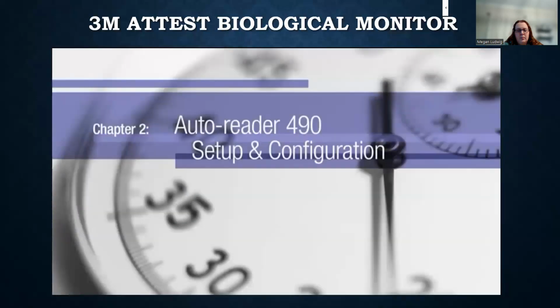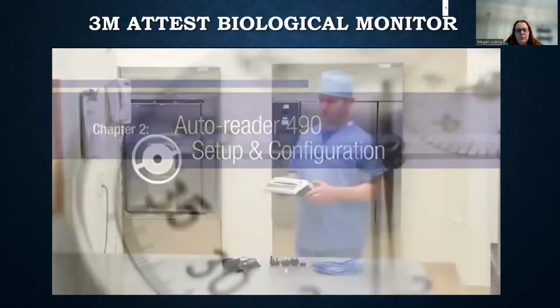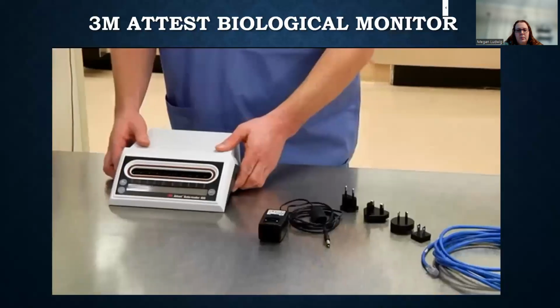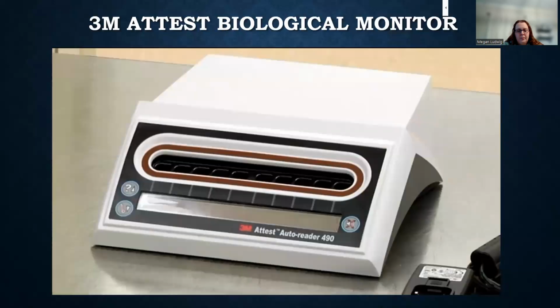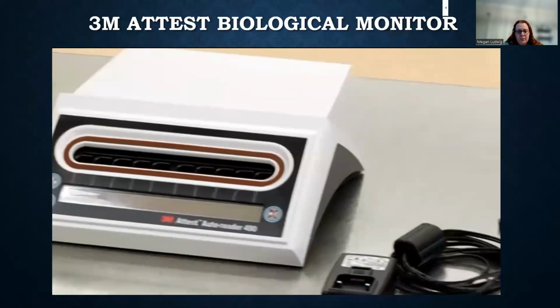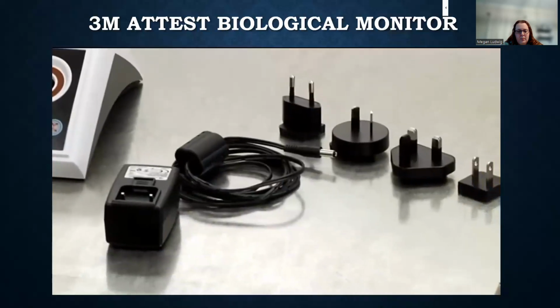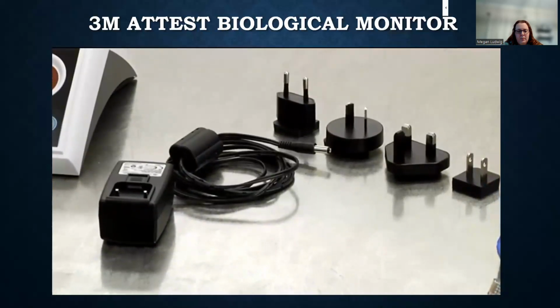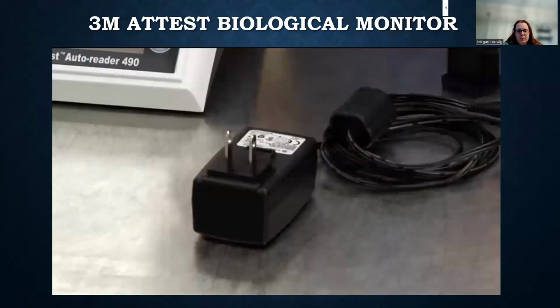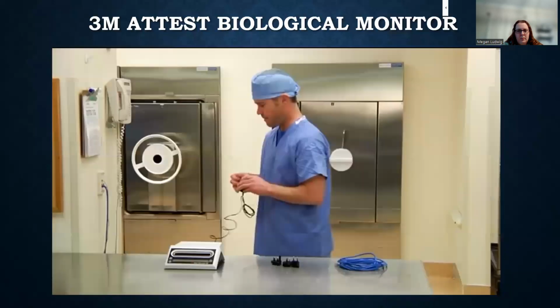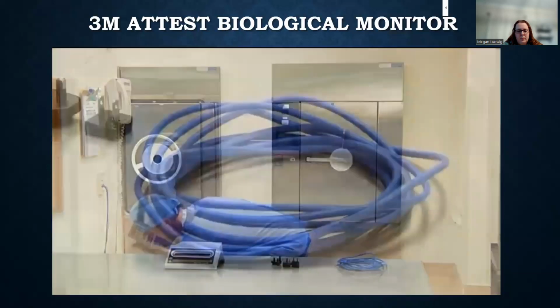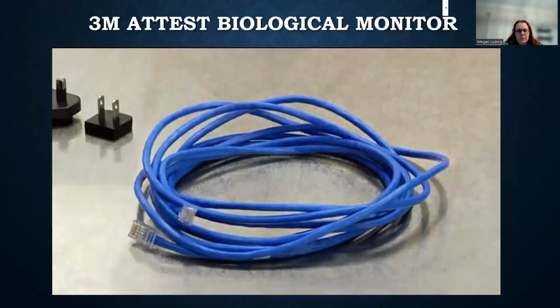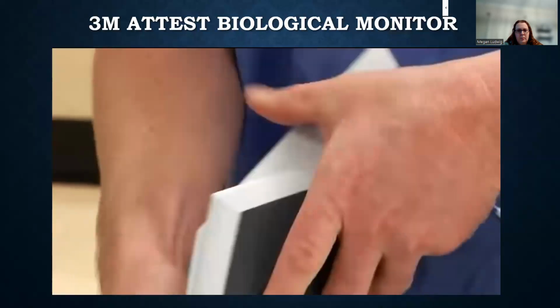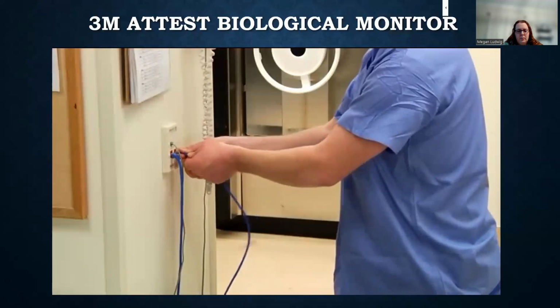Setting up and configuring your 3M Attest Auto-reader 490 is simple. First, place it on a firm, level surface near an outlet, away from sunlight and incandescent light. The Attest Auto-reader 490 comes with multiple power plugs for use in different countries. Select the plug appropriate for your country and insert it into an AC grounded outlet. If you plan to use the Attest web app, connect the supplied Ethernet cable to an Ethernet jack.